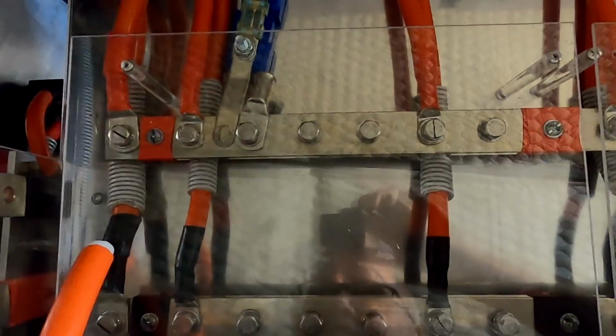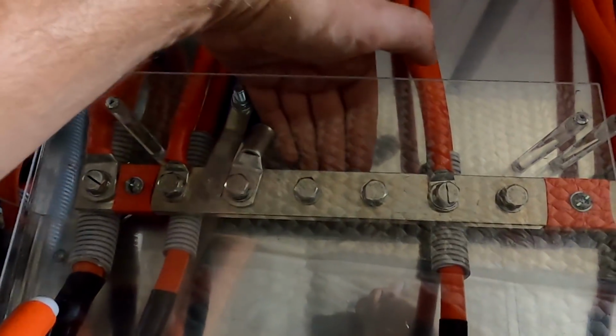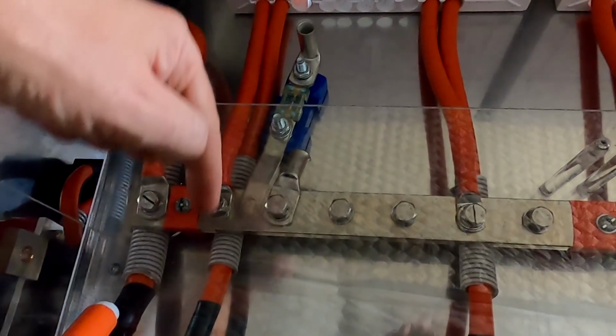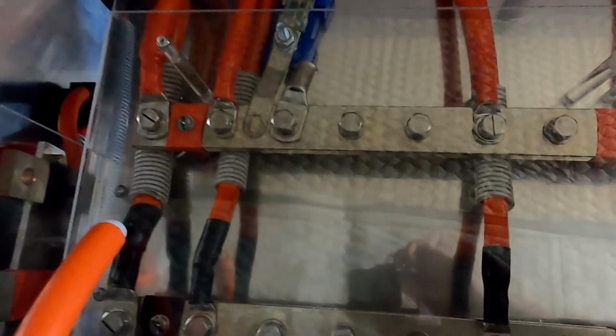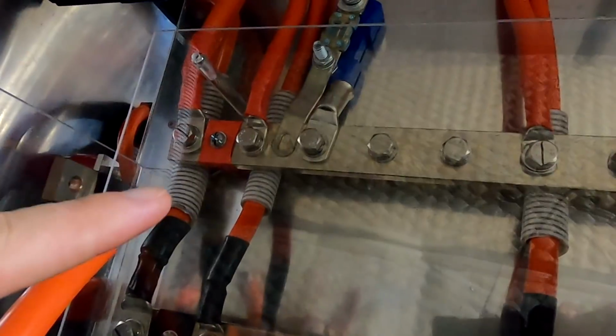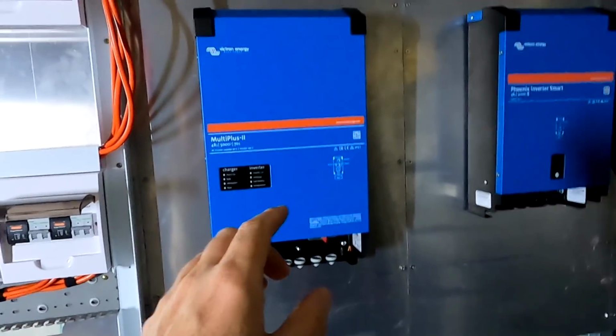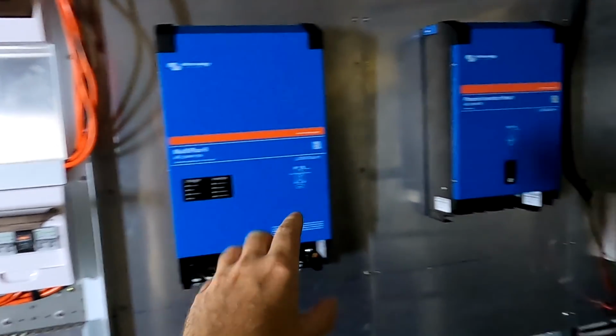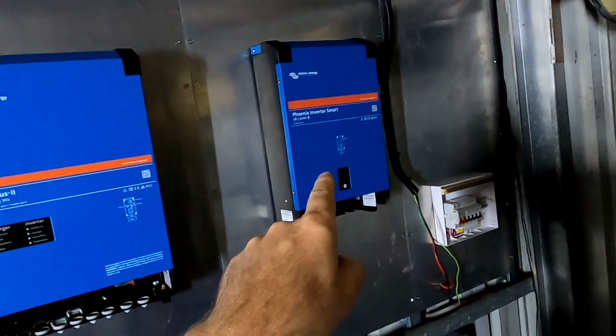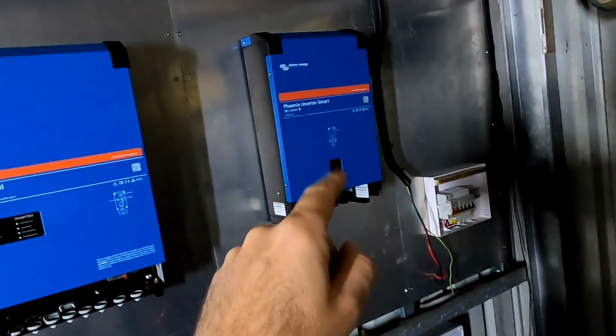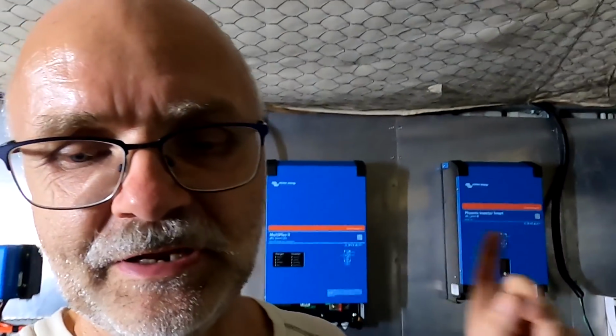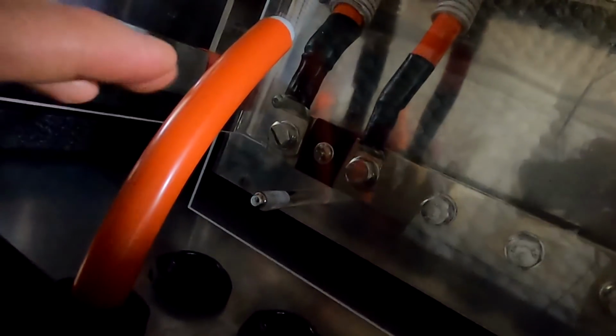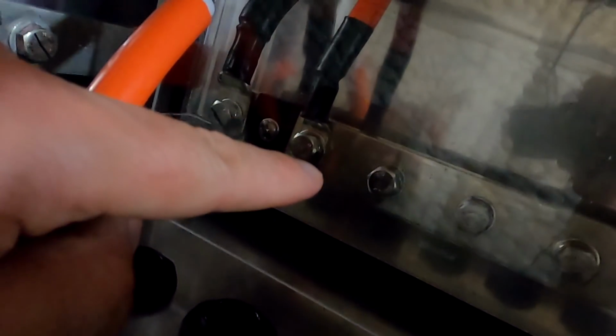I don't like the negative ducking under the positive and going in a big loop back to the negative - I don't quite like this. This problem only persists for the large inverter, the 5 kVA one. The smaller one is fine with a 63 amp circuit breaker in front, but for the big one we need the mega fuse with 200 amps, so we need to find another solution to connect our negative to this bus bar down here.